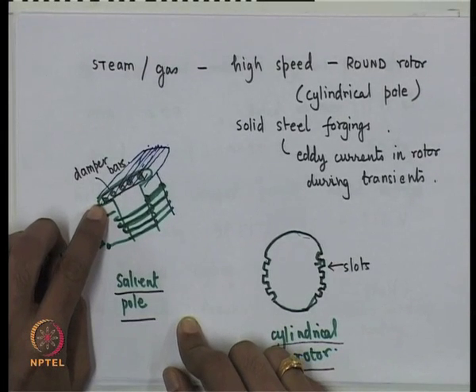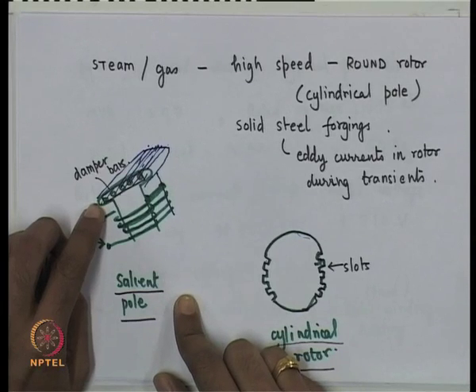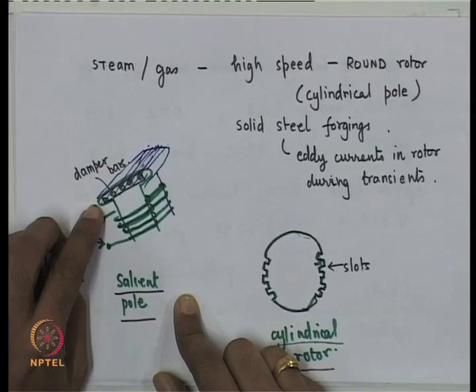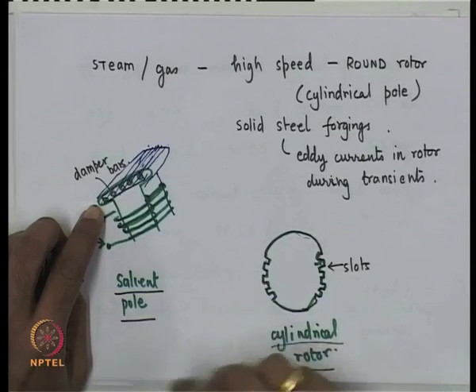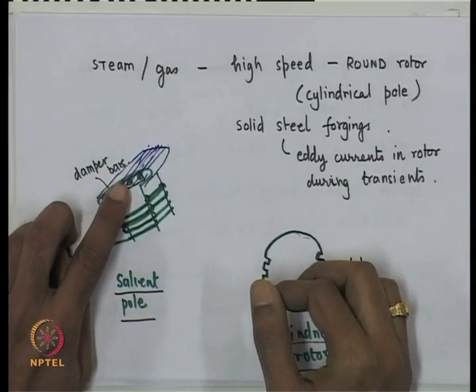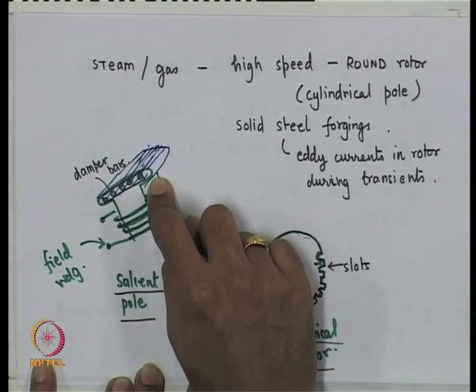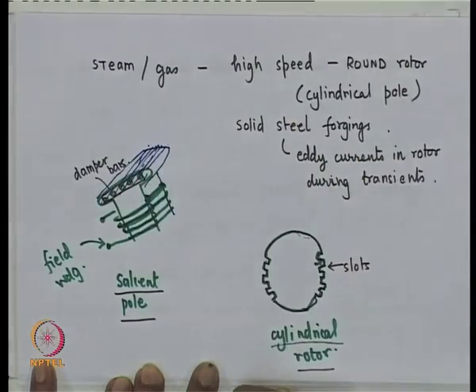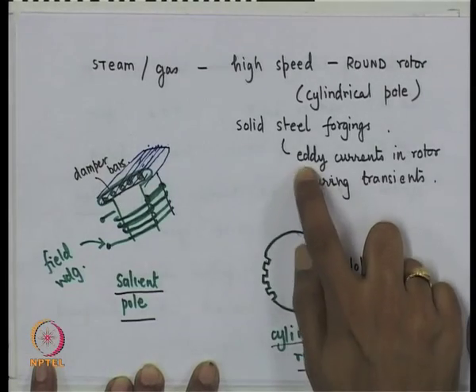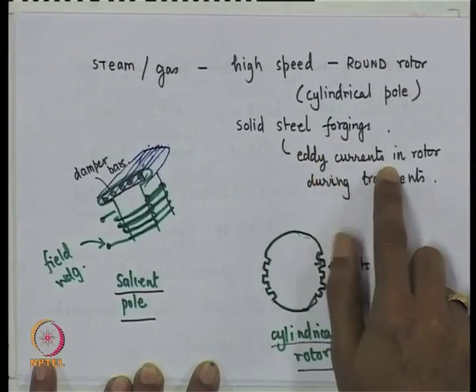The basic function of these damper bars is to damp out transients. Normally the flux created by the field winding, the three-phase rotating flux, and the rotary motion of the rotor are all at the same speed, so no EMFs are generated in the damper bars. But during transients, currents flow in them to damp out oscillations. In a cylindrical rotor machine, the solid steel body itself creates eddy currents which perform the same function.